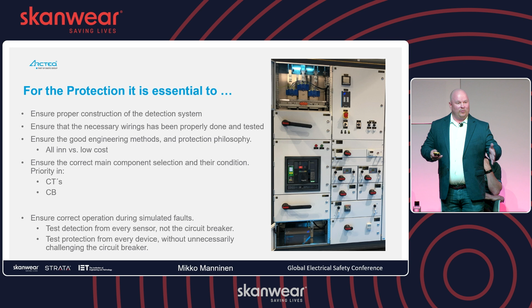For the protection, you need the detection. And for the protection, you need proper wiring. Wiring has to be correct. The circuit breaker has to be well maintained, in good condition. It has to be tested. If you have 120 sensors, do not test your breaker 120 times. It will break it. In the end, it will do the bad thing for the circuit breaker. So it's not the intention, but to do proper testing from the system, so that the system works.